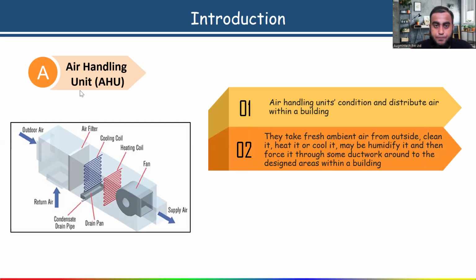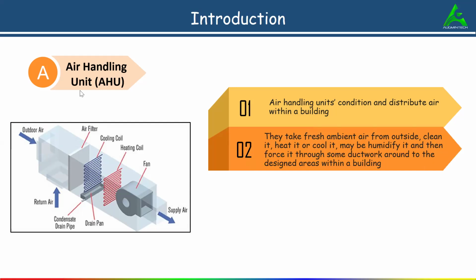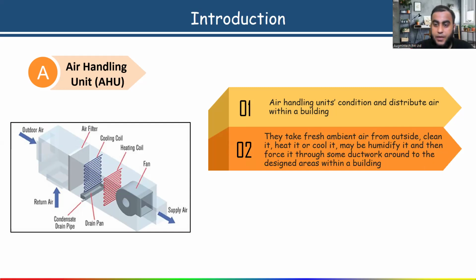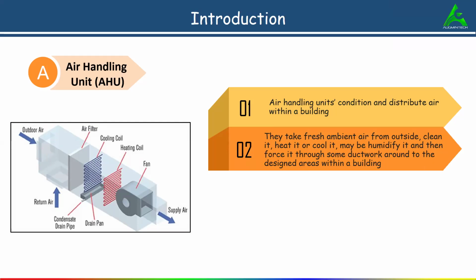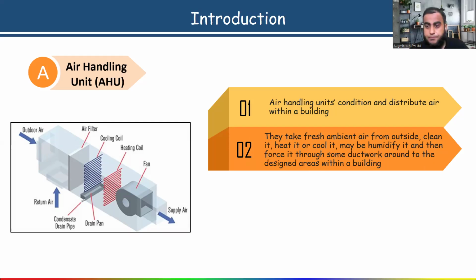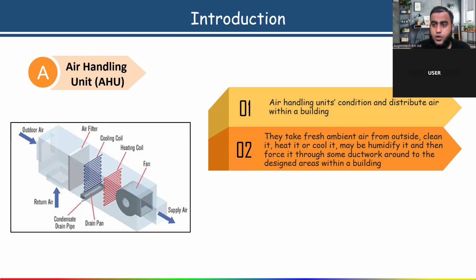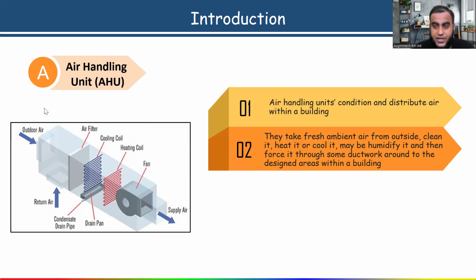They take fresh air. Okay. They take fresh ambient air from outside, clean it, heat it, or cool it, maybe humidify it, and then force it through some ductwork around to the designated areas within a building. Okay. So the main purpose of an air handling unit is what? They take the fresh ambient air from outside, then clean it, heat it or cool it, maybe humidify it.